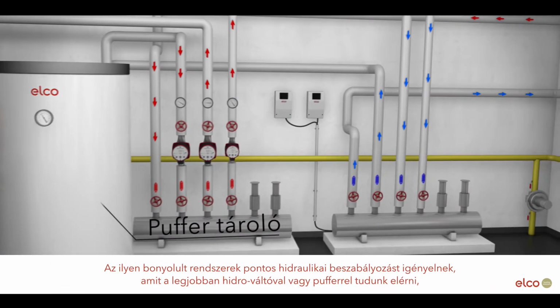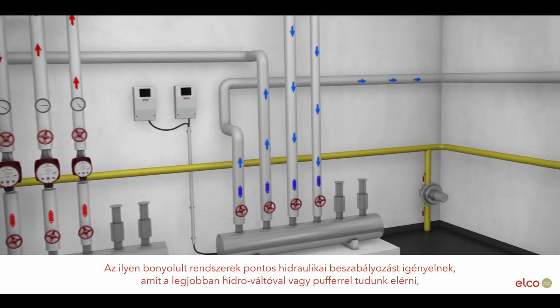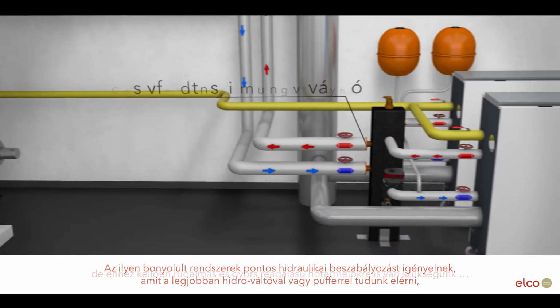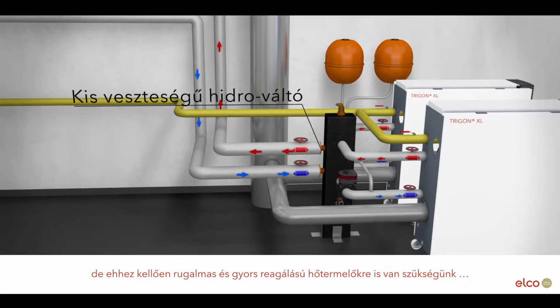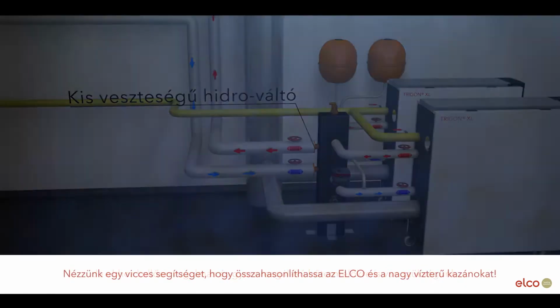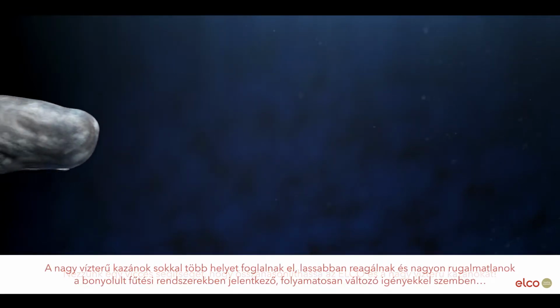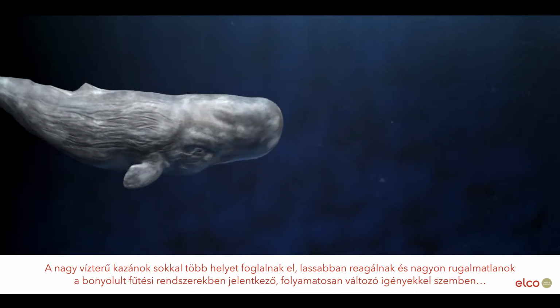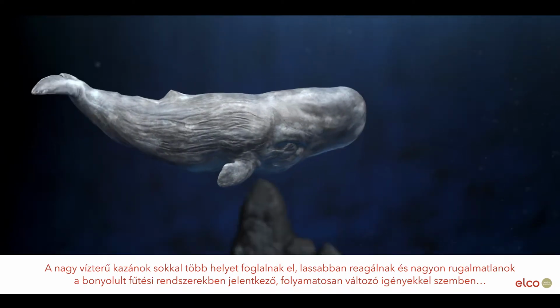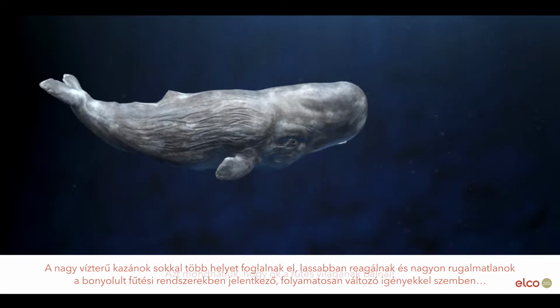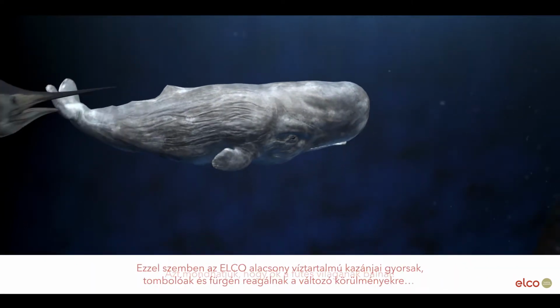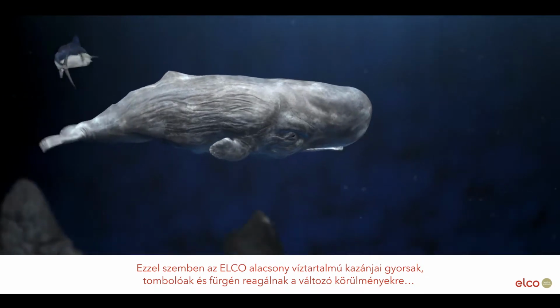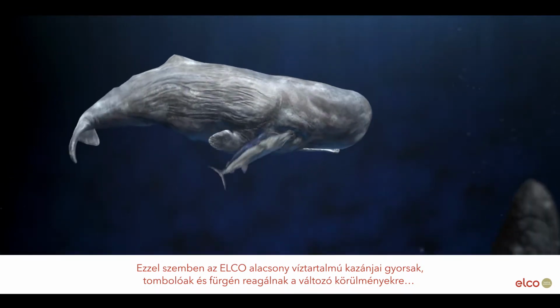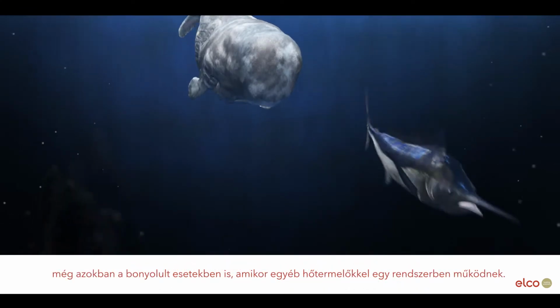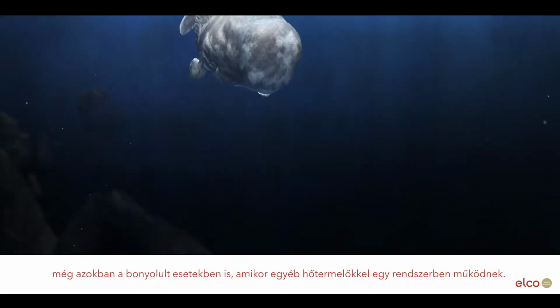This complexity requires proper hydraulic balancing, best done with a low-loss header or buffer, but also demands a certain flexibility and reaction time from the heat sources used. Here is a fun way to help comparing ELCO boilers to high water content boilers. High water content boilers are far bigger, slower to react and very inflexible to the changing demands of a heating system. They are the whales of the heating world. ELCO low water content boilers, on the other hand, are fast, furious and respond rapidly to changing circumstances, even in complex installations when being combined with other heat sources.